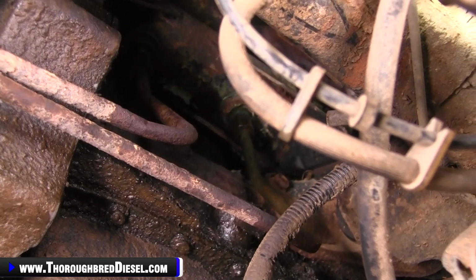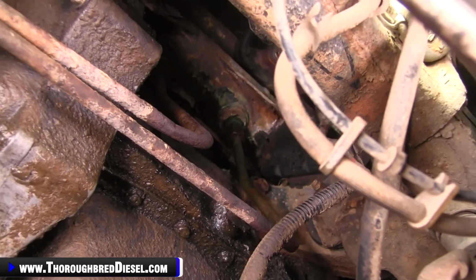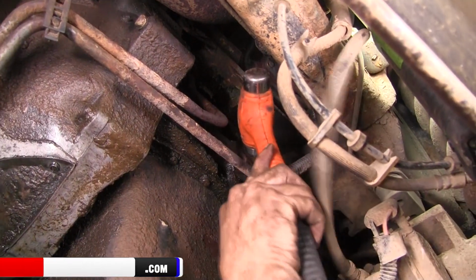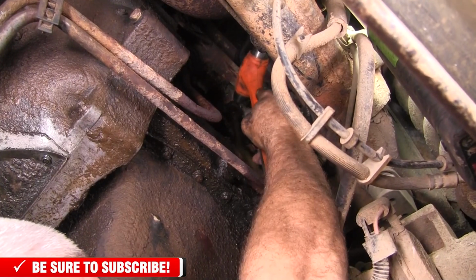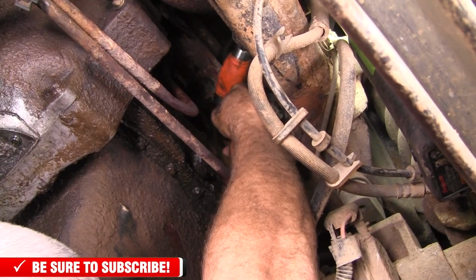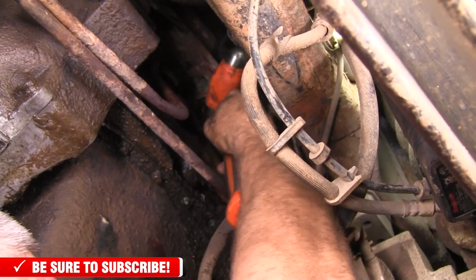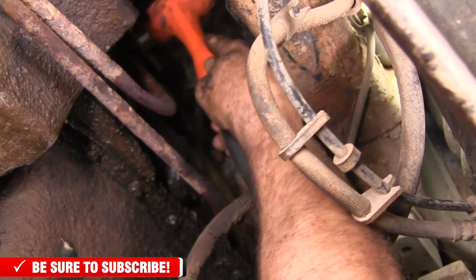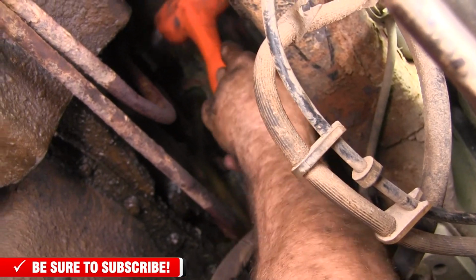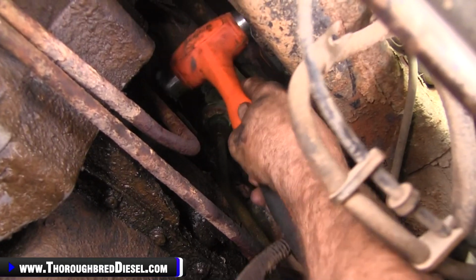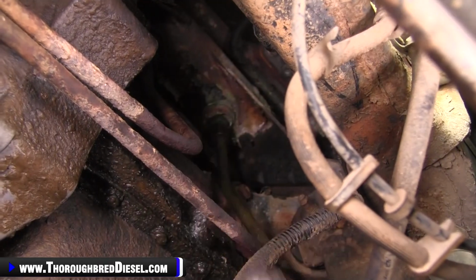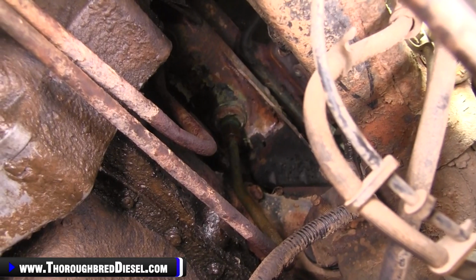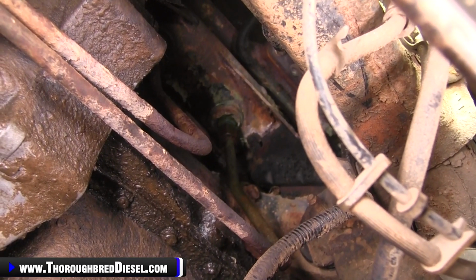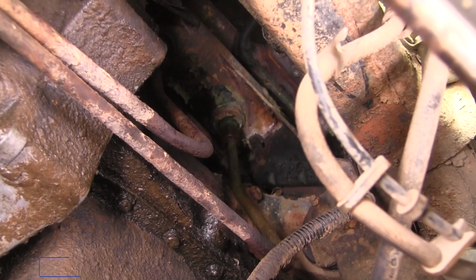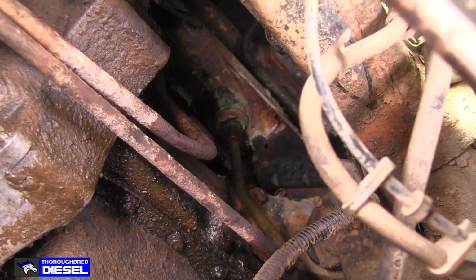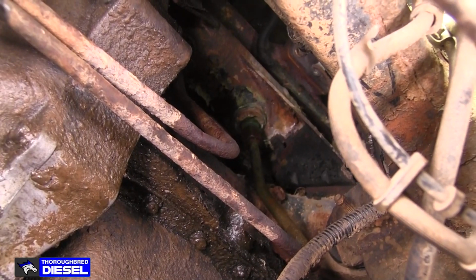Here's what you do: soak it down with penetrating oil. What I like to do when I'm ready to work on this is come in with a hammer and tap lightly around the fitting itself, hoping that breaks some of the corrosion loose between the line and the nut. Getting it broken loose from the heat exchanger isn't really the problem — it's the line corroding to the nut. If you're lucky enough to have a line wrench, it's really going to be your friend with this fitting, and I'll show you exactly how I used it.